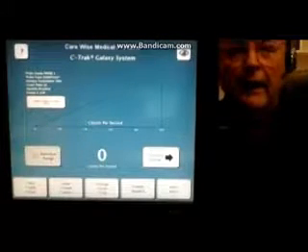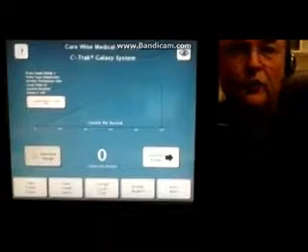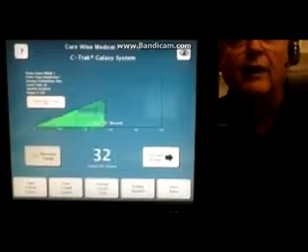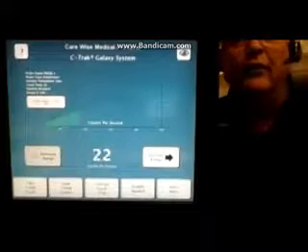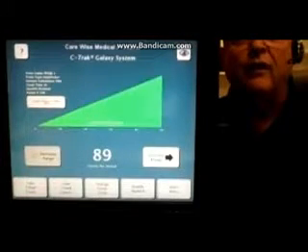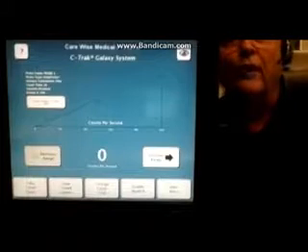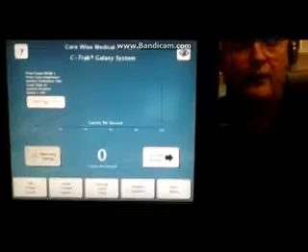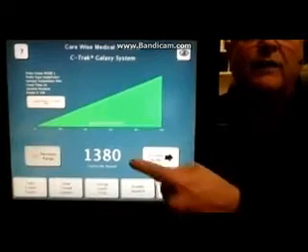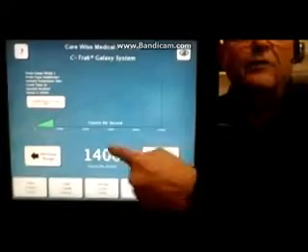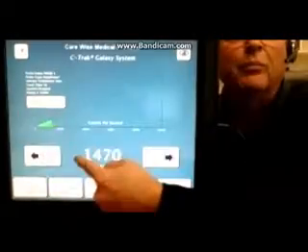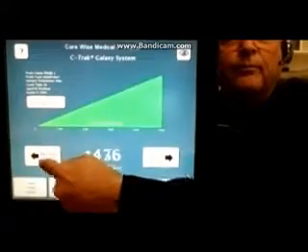According to how strong the dose is in your patient, sometimes the 0 to 100 scale that we're in now might work just fine. You always get the actual count number there where it says counts per second. So even if I change my range, the counts per second stays the same. It's just that the display and the sound changes.